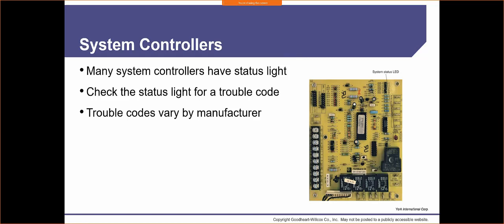So if you pull the panel off to get to the board, somewhere on one of those panels there should be a sticker. On that sticker, it's going to tell you how many flashes equal what part of the system or of operation. So if we have a solid light, that may indicate that our system is running fine. But if we get 3 short flashes and 5 long flashes, that may mean code 35, and that 35 could indicate a pressure switch fault. Cool. Now we know that we have an issue related to our pressure switch, and we need to figure out what. And knowing the sequence of operation, we're going to be able to address that issue.